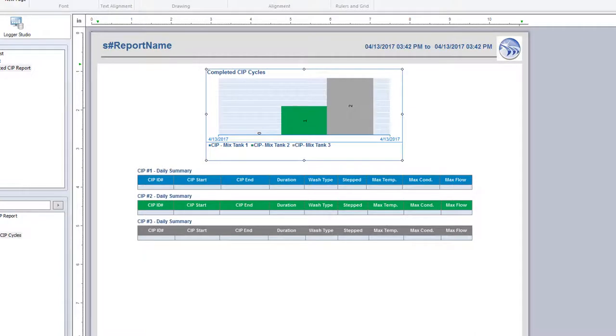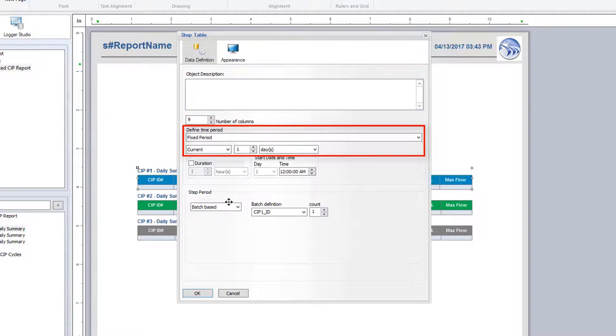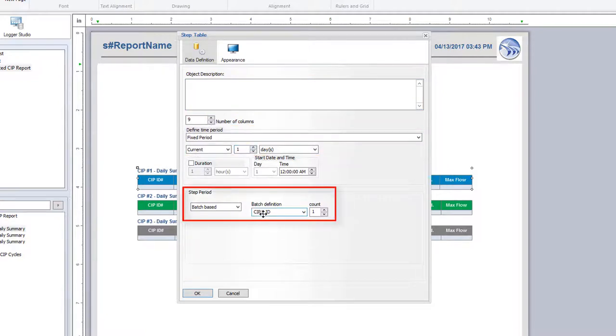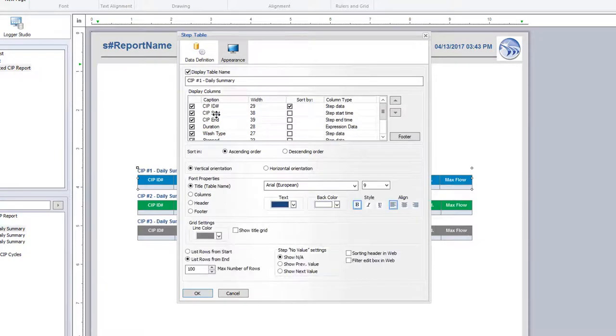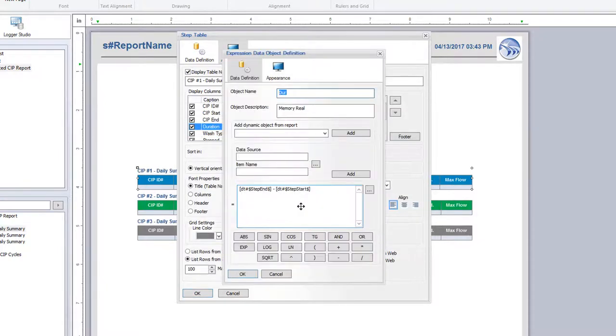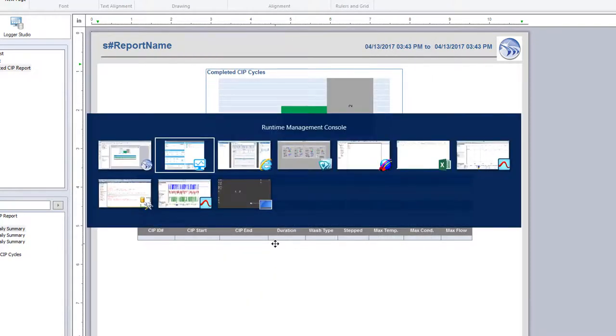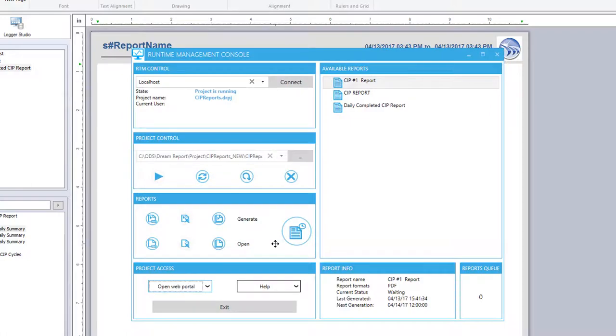For the tables, I use a step table, set for the current one day, and the step interval being based on each batch or CIP ID that ran. For each CIP, show the start and end times, calculate a duration, and show a few other key calculations. You could then set this report to run automatically every day, month, etc. to summarize your CIP activity.